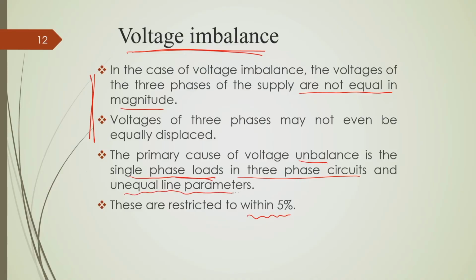But since different types of customers are connected in different phases, it is eventually not possible to have an identical loading in all the 3 phases. So, at that time this unbalance or imbalance will occur. Similarly, when we have distribution lines with unequal line parameters, there is unequal voltage drop due to this unequal impedance of the line, which is caused by unequal spacing of the phases. Primarily due to this unequal spacing of the phases, we may have this type of problem.